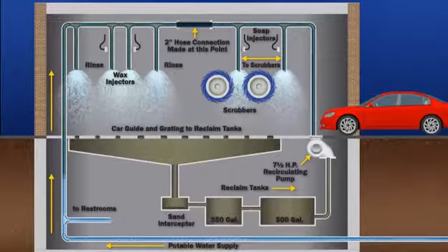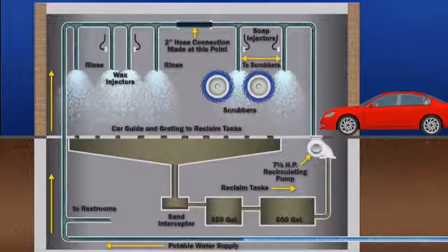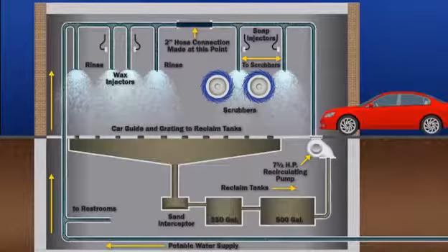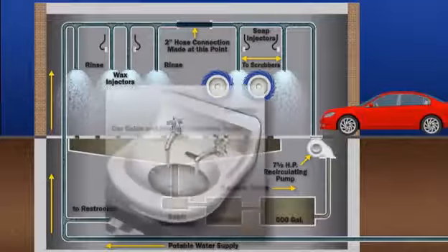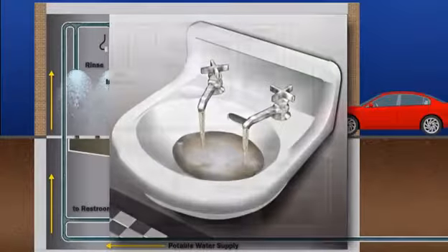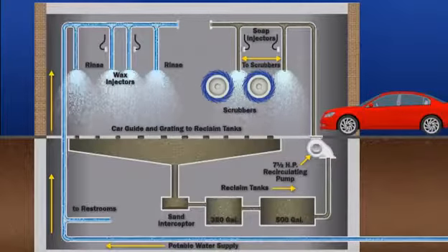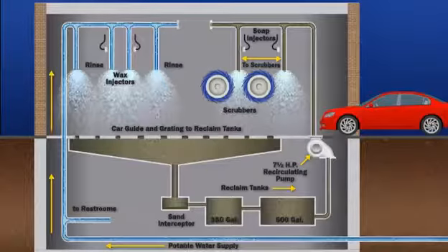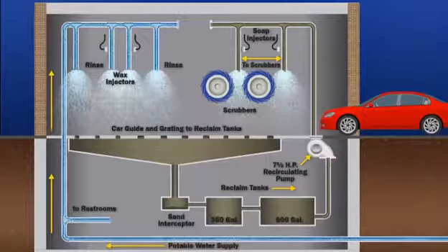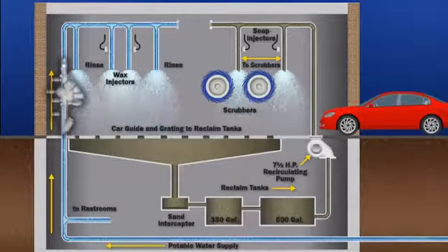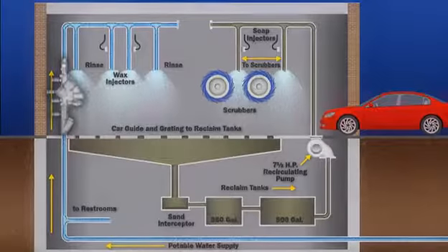The pump forced the contents of the 2 reclaimed tanks, 850 gallons, into the drinking water main. It didn't take long before a car wash employee noticed brown soapy water in the restroom. The cross-connected 2-inch hose was immediately removed, but not before contaminating an 8-block area. The water mains were flushed and chlorinated by the water department. A reduced pressure principle backflow prevention device was ordered installed on the water service pipe to provide premise isolation.